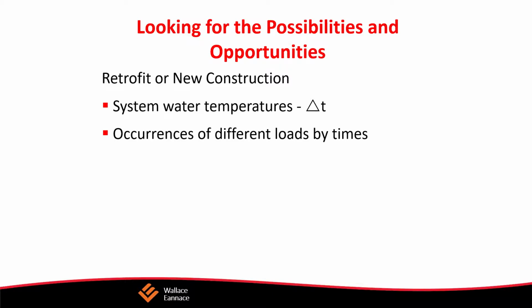One of the things we look at is system water temperatures. That is the delta T. The higher the delta T, the more efficient the system will run. If we can provide the comfort with higher delta Ts, we will be able to absorb more energy and have the system run more efficiently.